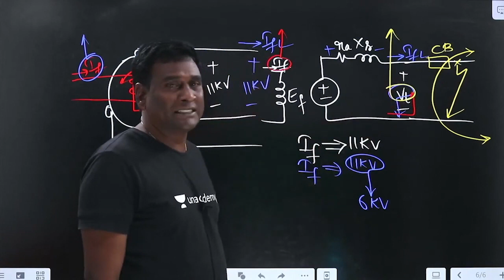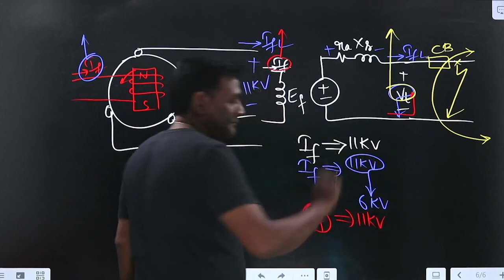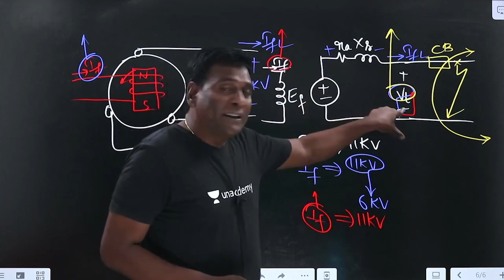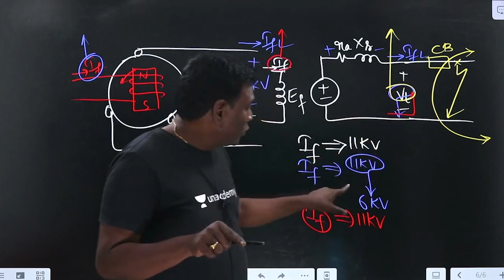Then with red condition, you are increasing the field current such that my terminal voltage is going to be 11 kV only. Field current is increased. Now under no load conditions, with this IF, 11 kV would come here. And the moment it is loaded, my terminal voltage is dropped to 6 kV. Now in order to compensate that, I am forced to increase my field current such that terminal voltage is 11 kV. Now with yellow, what happened?